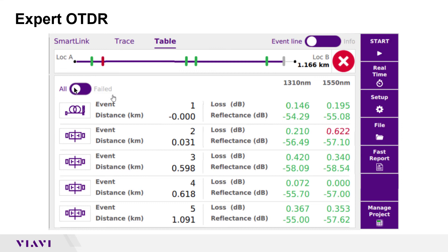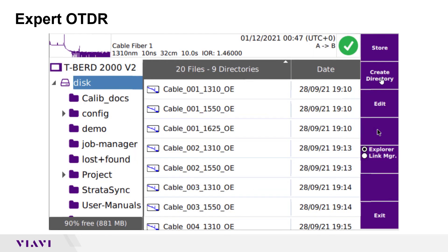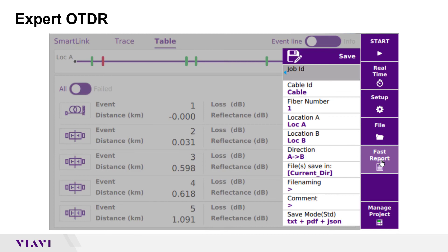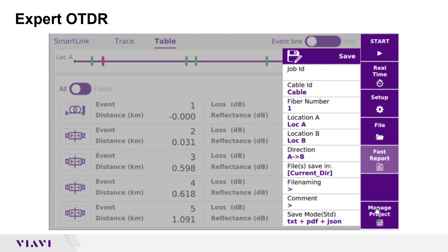If you wish to save a report, the first step is to specify the directory. Tap the file soft key and either create a directory or select the directory into which you want to save your results. Tap exit, then tap the fast report soft key. Enter your cable number, fiber number, location, and direction, and tap save. Tap the check mark to accept the default file name and save the test results. Tap fast report again to return to the results display from which you can test your next fiber.